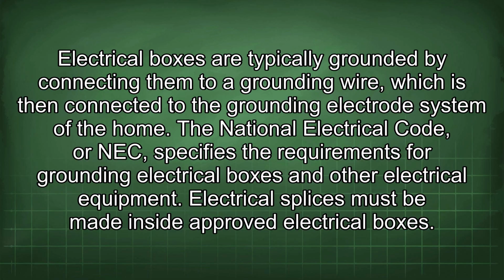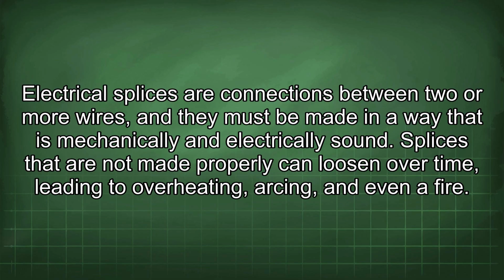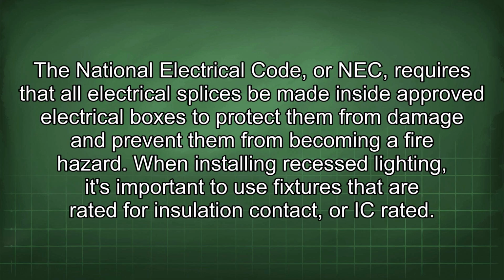Electrical splices must be made inside approved electrical boxes. Electrical splices are connections between two or more wires, and they must be made in a way that is mechanically and electrically sound. Splices that are not made properly can loosen over time, leading to overheating, arcing, and even a fire. The National Electrical Code, or NEC, requires that all electrical splices be made inside approved electrical boxes to protect them from damage and prevent them from becoming a fire hazard.